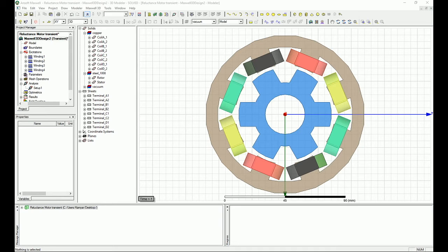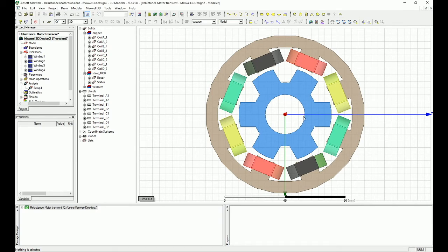Let's go ahead and show you how to simplify this model, which does not look quite symmetric to me. You could say we can make this one-fourth or one-sixteenth, but at the moment this design is not totally symmetric — if you look at the rotor, it's not perfectly aligned with the poles, and if you cut it, some parts have teeth and others don't. So what you want to do is change the rotor a bit, and also the stator with the coils, and then you can get a better split point.